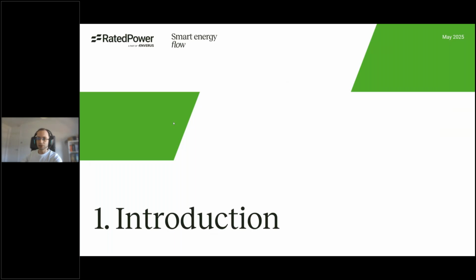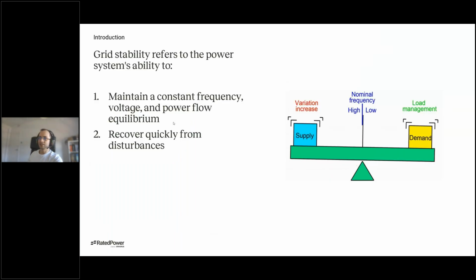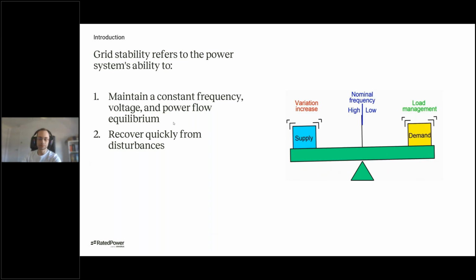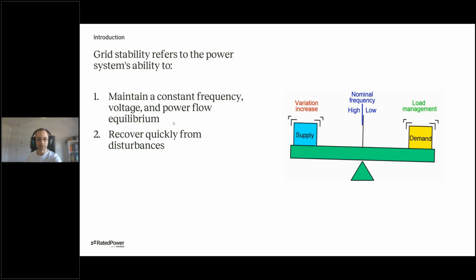So to begin with, a small introduction, and I would like to present the concept of grid stability. Grid stability basically refers to the power system's ability to do two things. The first one is to maintain a constant frequency, voltage, and power flow equilibrium. This means that here in Europe we have 50 hertz, for example, so the target is to work around this 50 hertz. That's the first objective of grid stability. And the second one is to recover quickly from disturbances. So if there's a fault in a transmission line or in a generator, the grid should be able to stabilize using different generators or different services to reach this equilibrium back. And here is where ancillary services come into place.